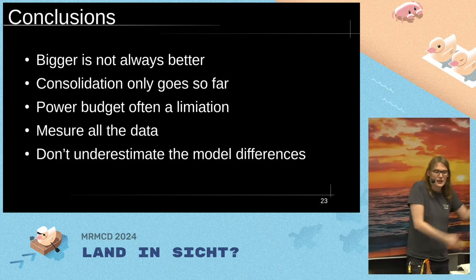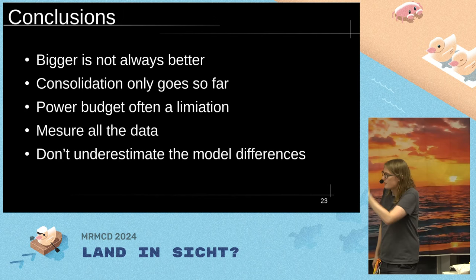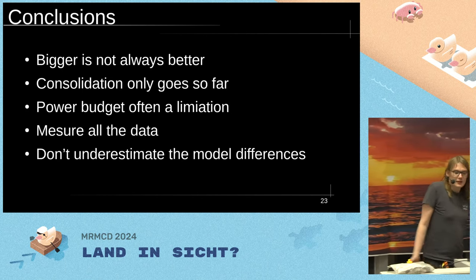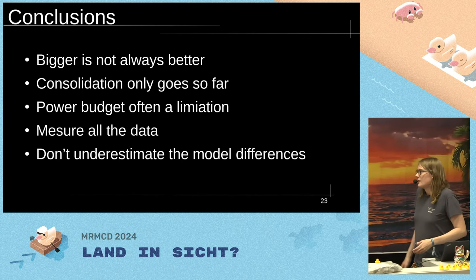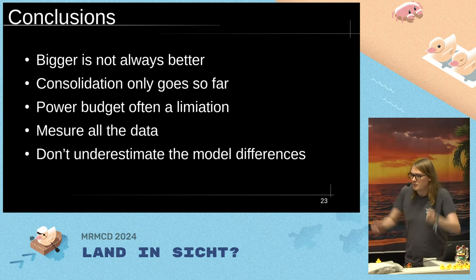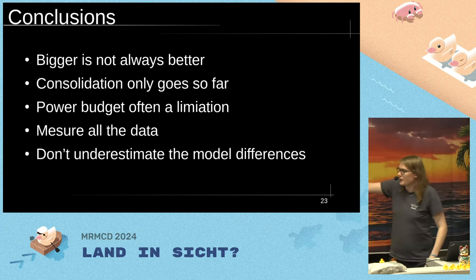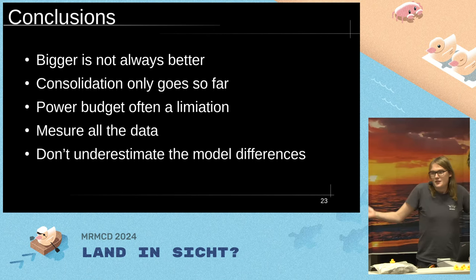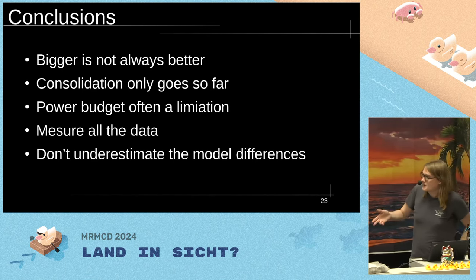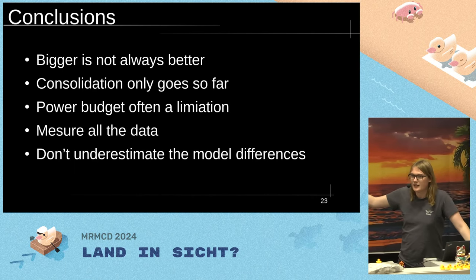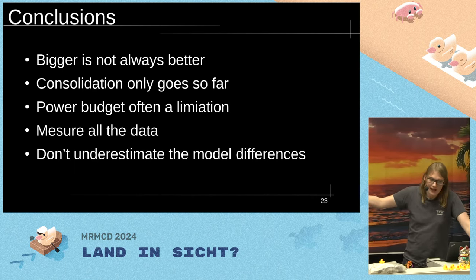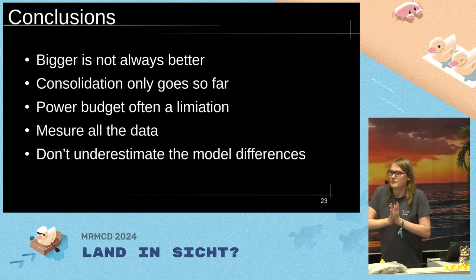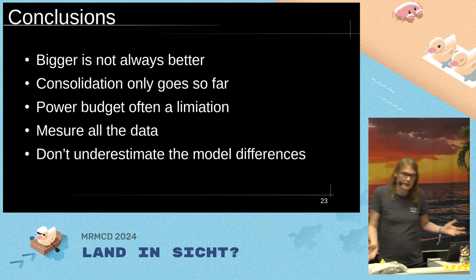In a lot of data centers, the power budget per rack is the real limitation — for example, 5 or 10 kilowatts per rack. We have a few racks at work with high-density servers where only two servers fill the entire power budget. So consolidating onto one powerful server doesn't always help. And: always measure everything. Don't underestimate the differences between vendors — compare them thoroughly before buying.